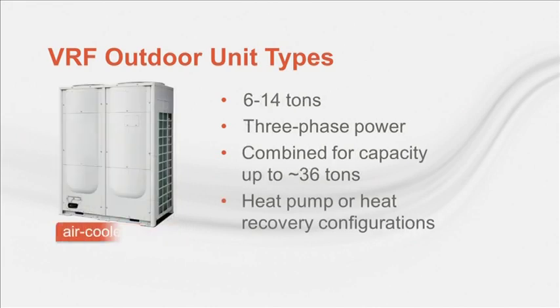For conventional VRF systems, probably the most common type of outdoor unit is an air-cooled model depicted here. These units are offered in 3-phase power and, depending on the size, will have 1 or 2 upflow discharge condenser fans. They are modular, with single units offered in distinct capacity increments, typically from 6 through 14 tons. Individual outdoor units can be combined together into 2 or 3 unit modules for total capacity up to around 36 tons, depending on the manufacturer. Buildings larger than 36 tons can still use VRF, but would need to be split up to be served by more than one system.